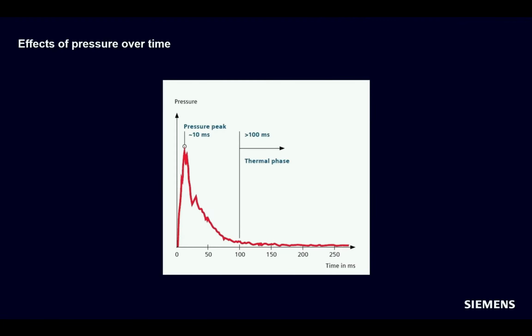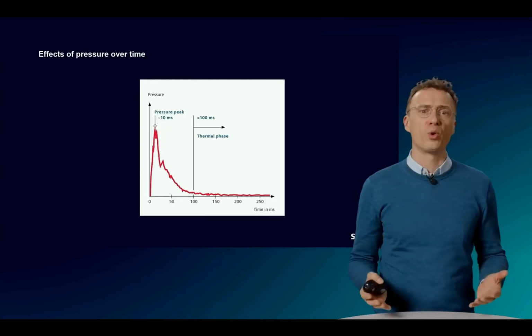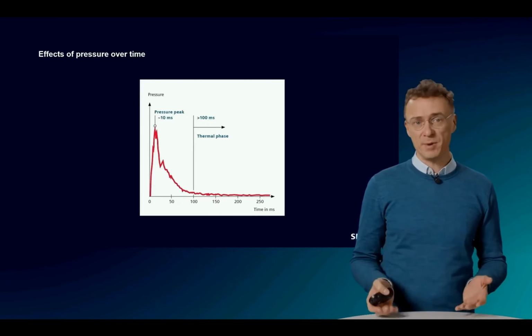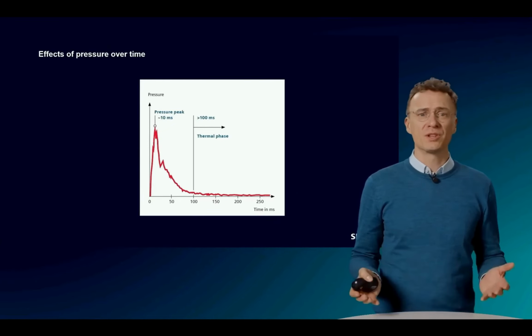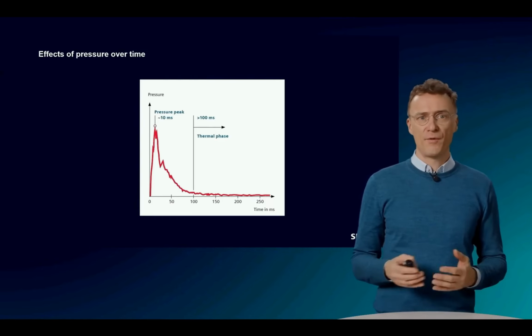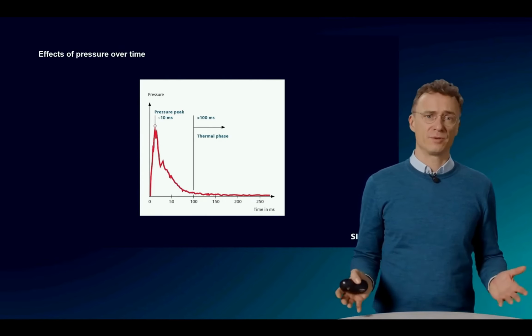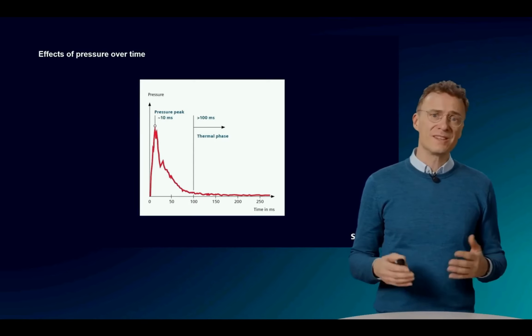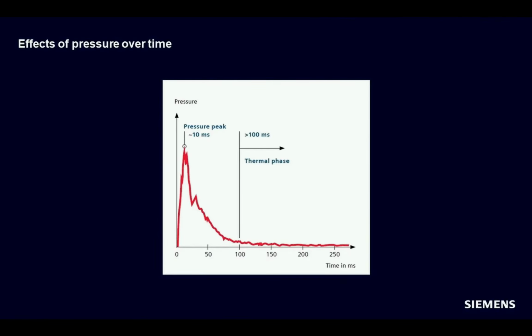What does the quenching device do? Well, the device causes an all-pole short circuit on the main bus bar. This short circuit immediately removes the energy from the arc fault and the arc goes out. The resulting short circuit is now switched off by the circuit breaker.